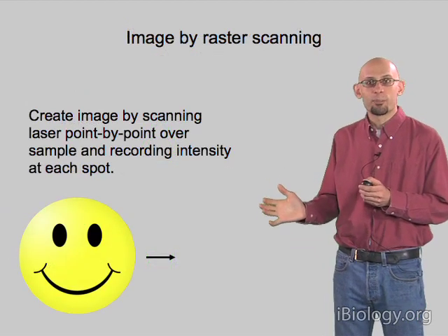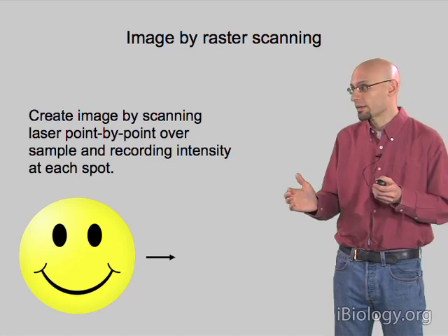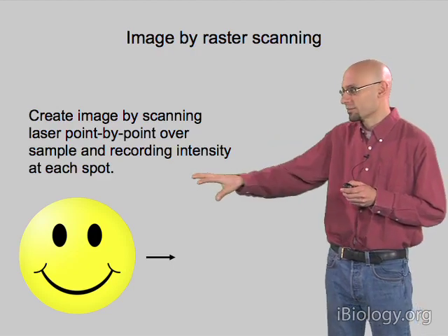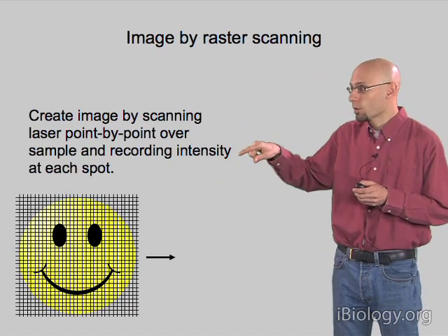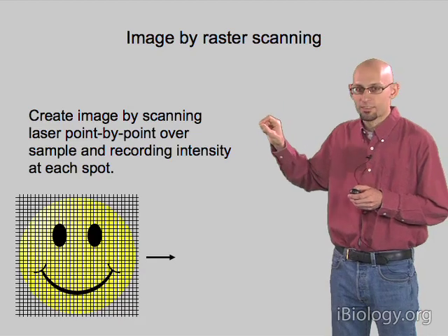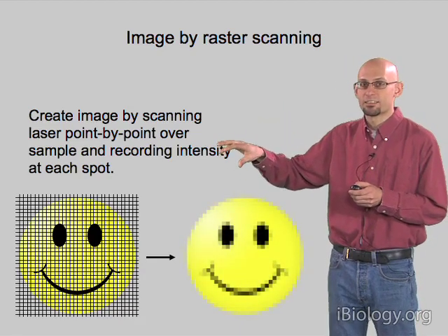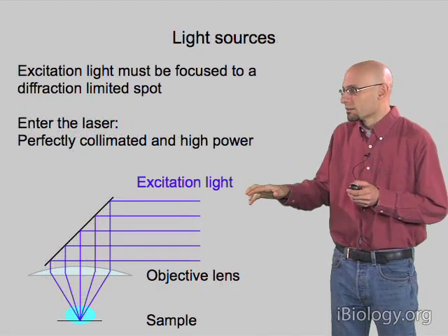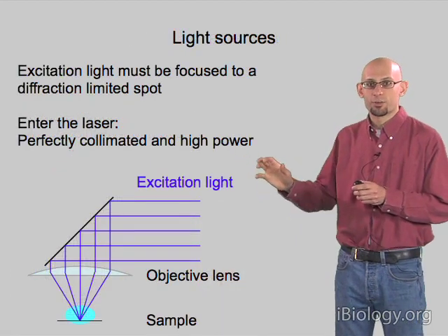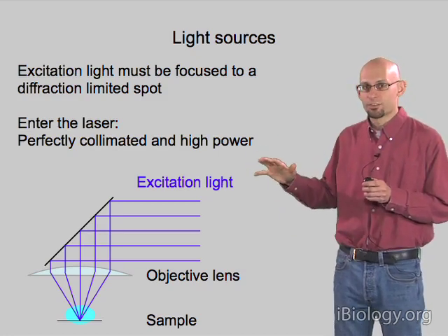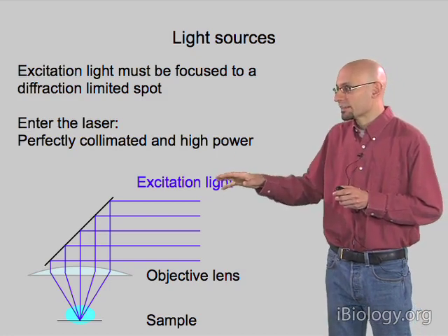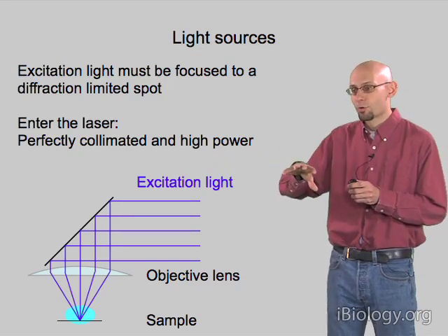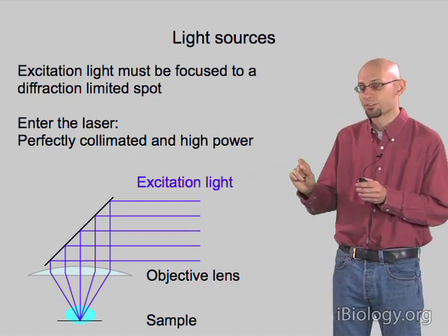The problem now is we're only imaging a single spot, and to get an image you need more than a single point. The way we solve that is by recording lots of different points in our sample arrayed across it — marching the laser spot across the sample point by point, and using that to record the intensity at each spot and reconstruct the image as a 2D grid. We use a laser because it gives highly collimated illumination and high power so we can quickly record the fluorescence from each spot.